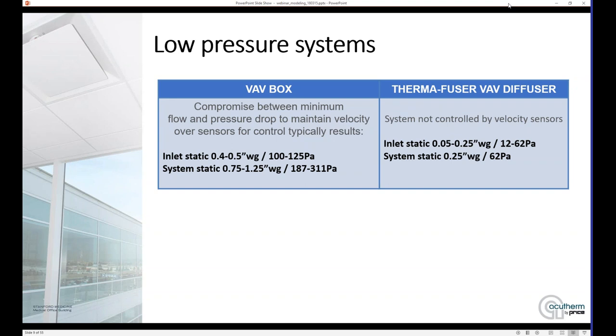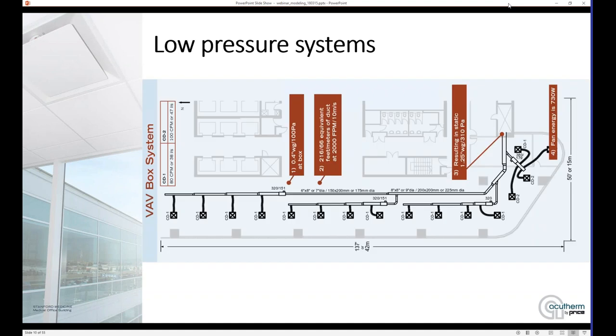However, with the Thermafuser diffuser approach, if you're looking at an all-low-pressure system, it's not being controlled by velocity sensors. There is pressure control in the system, but that is done by static pressure, which can be measured much easier and much lower. So now we're looking at inlet statics of anywhere from 0.05 to 0.25. In this part of the system, we're not looking at a pressure higher than 0.25. So now we've got a system static of 0.25 compared to a system static with a box of anywhere from three-quarter to 1.25 inches.